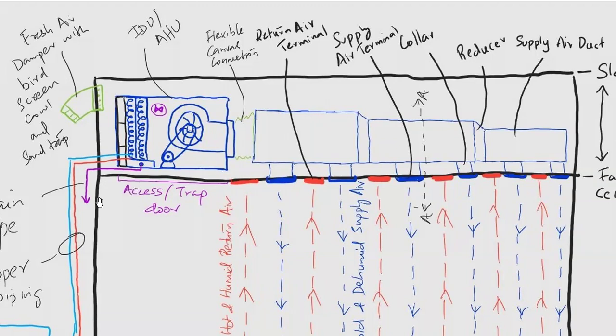Okay. Then later you can see at the bottom of the machine some connections are made on the false ceiling, called an access door or trapdoor connection. So what is the purpose of the access door or trapdoor? Suppose you get some problem inside the machine, especially on the filter side, maybe even on the fan side. We can't deliberately crack the entire false ceiling and look at the machine, can we? We can't do that under normal conditions. So that's why we provide an access door or trapdoor connection.